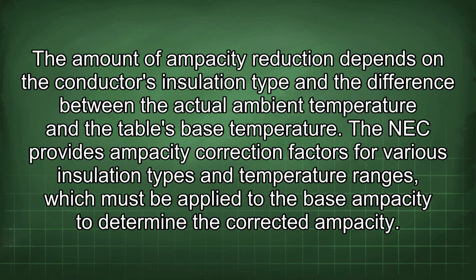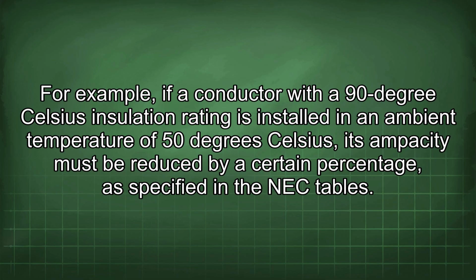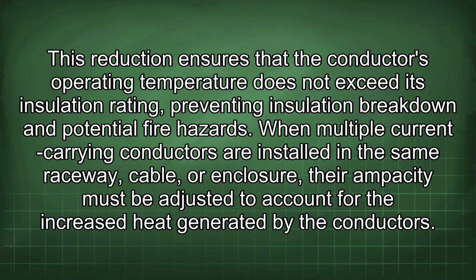The amount of ampacity reduction depends on the conductor's insulation type and the difference between the actual ambient temperature and the table's base temperature. The NEC provides ampacity correction factors for various insulation types and temperature ranges, which must be applied to the base ampacity to determine the corrected ampacity. For example, if a conductor with a 90°C insulation rating is installed in an ambient temperature of 50°C, its ampacity must be reduced by a certain percentage, as specified in the NEC tables. This reduction ensures that the conductor's operating temperature does not exceed its insulation rating, preventing insulation breakdown and potential fire hazards.